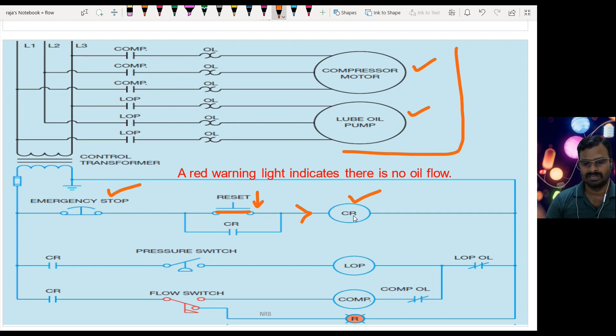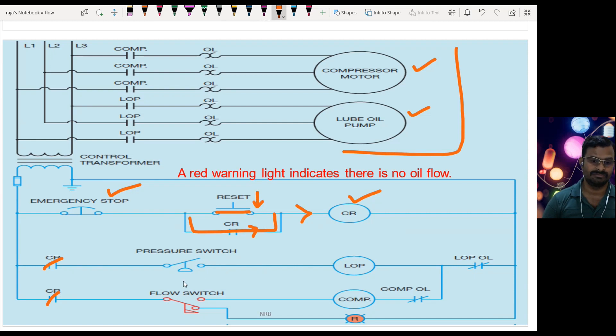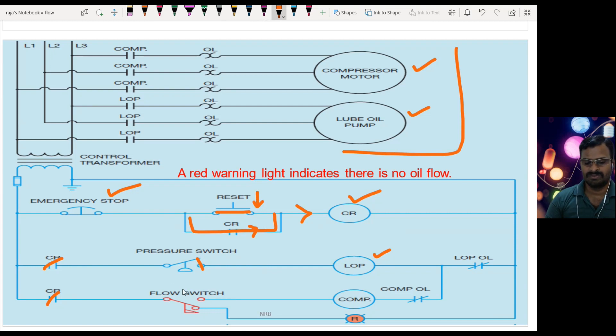When the control relay is energized, current flows through this path and the switches get closed — now the system is ready and waiting for the pressure switch to reach the set pressure. When the pressure reaches the set level, the pressure switch automatically closes. When the pressure switch closes, the lube oil pump turns on. Once the lube oil pump is on, the flow of liquid is detected using the liquid flow switch.